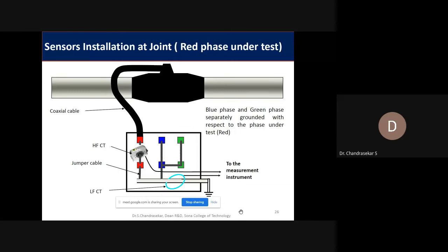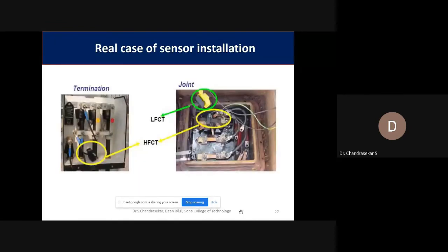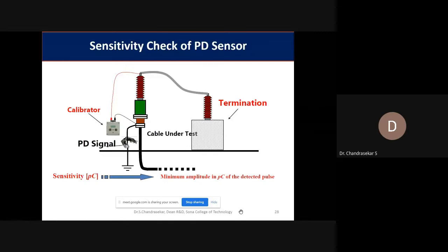So this is the type of sensor connection at joints. Okay, so if it is a 3-core cable, a 3-phase cable, then for example, if the red phase is under test, then we connect the HFCT sensor in the red phase, and both the blue and green phases are short circuited. So we can easily measure what is happening in the red phase. Okay, so while measuring one phase, the other 2 phases should be short circuited in order to avoid false readings. So these are some real pictures of the terminations and joints, showing how the sensors are connected.